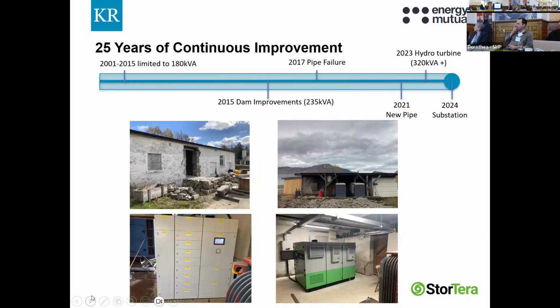This battery storage system does two things. It supports the diesel generators, so we don't need a larger diesel generator, helping with peak power and fuel efficiency, and it also works with the hydro scheme. We can put the hydropower scheme into water conservation mode, reducing the amount of water passing through the turbine, while the battery picks up grid control and frequency control on the network, giving us water efficiency.